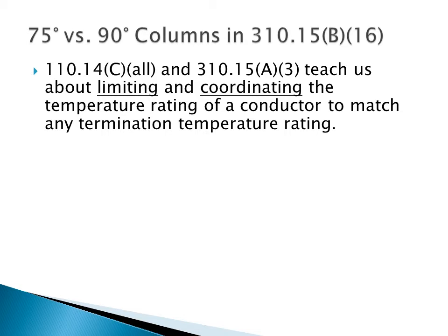And since in the world 95% of the terminations are rated for 75 degrees, the curriculum has chosen to make you assume that all temperature ratings of terminations are at 75 degrees. So our world is going to be the 75-degree column when we're talking about circuits, except of course those adjustments and corrections that I told you about a second ago.